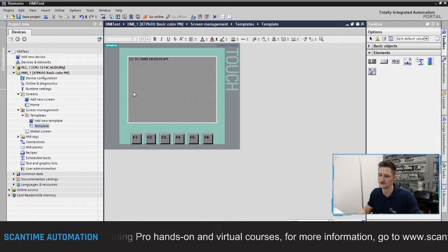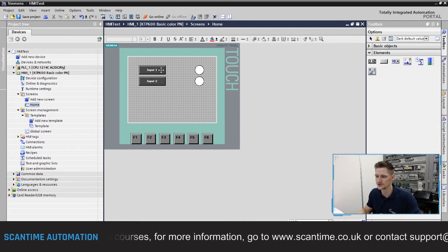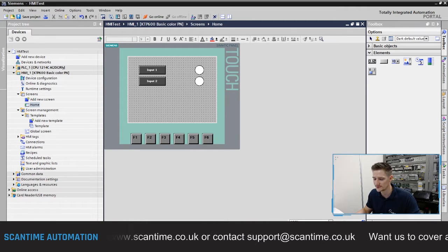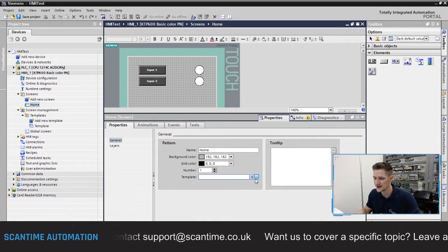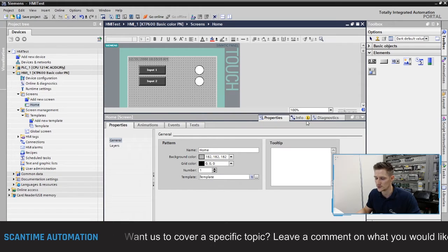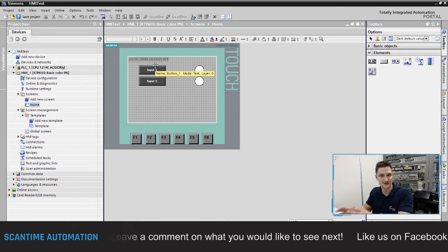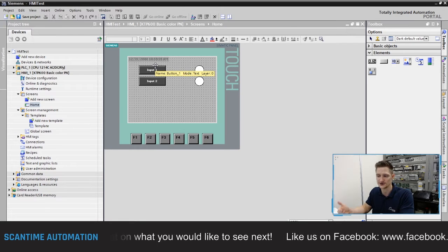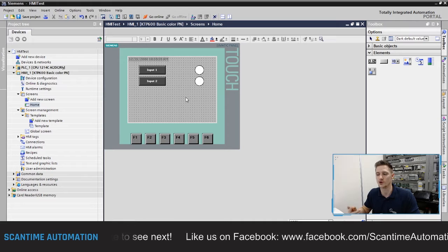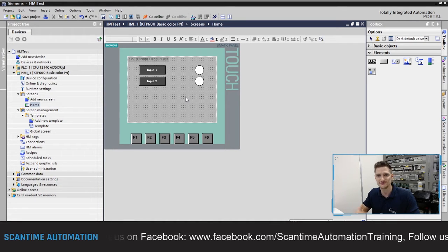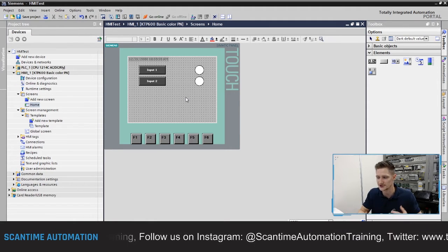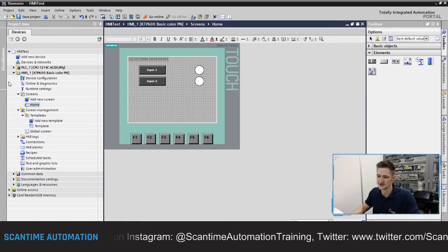Now that the template is created with the date and time in the top left, if I go to the home screen you'll notice it hasn't updated — that's because it's not yet using the template. Go to properties, expand the three dots, find the template option, and tick it. The screen now updates. Note the date and time looks slightly faded on this screen — that's expected since it belongs to the template layer. Next, I'll create two more screens: one for control and one for alarms.